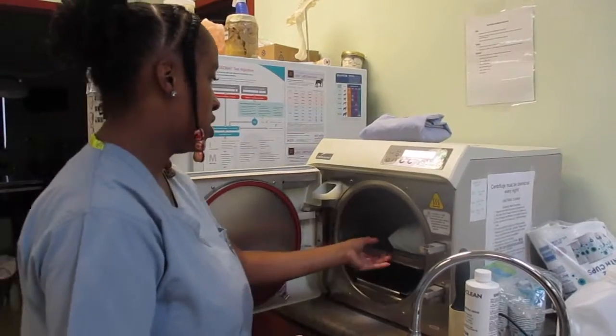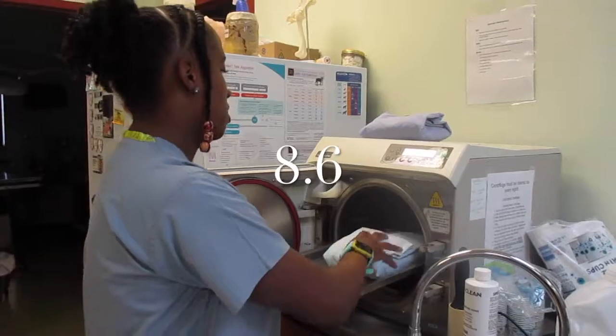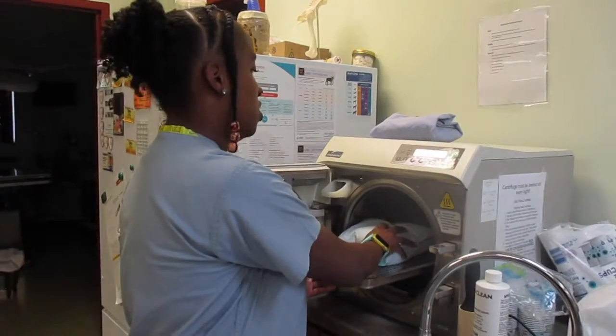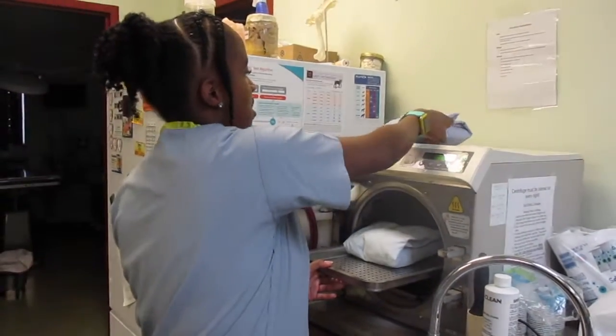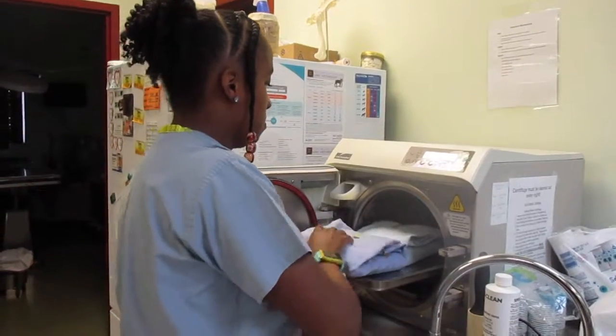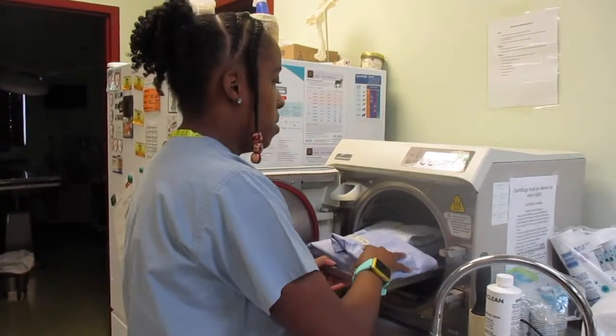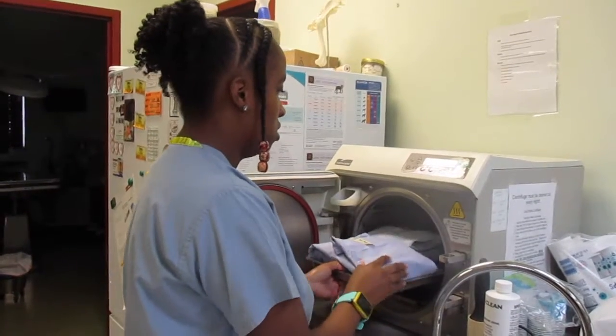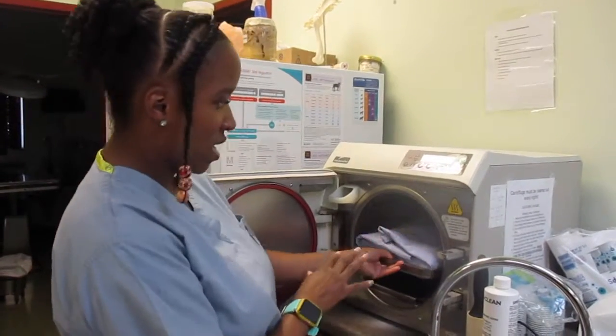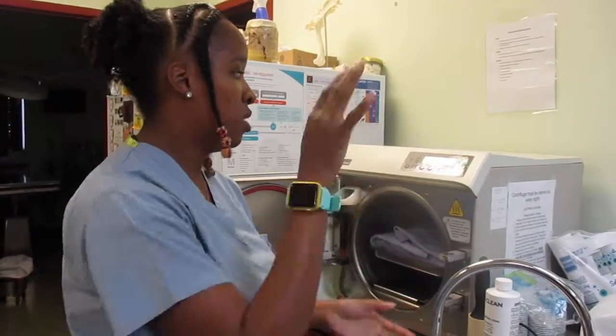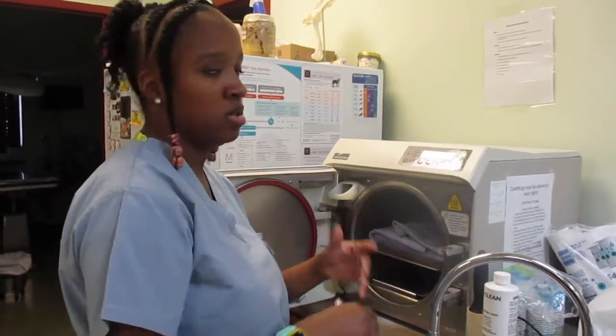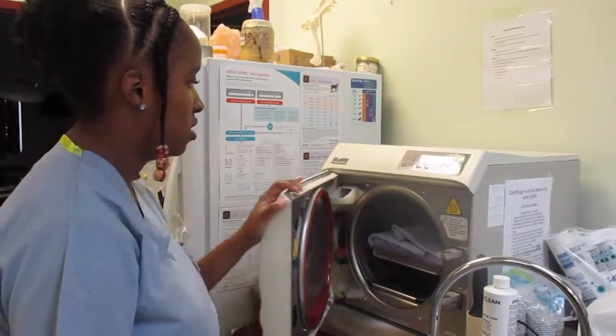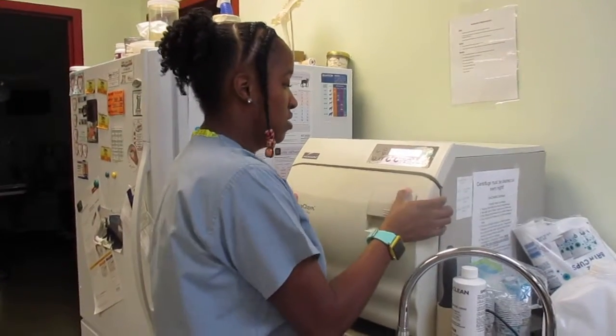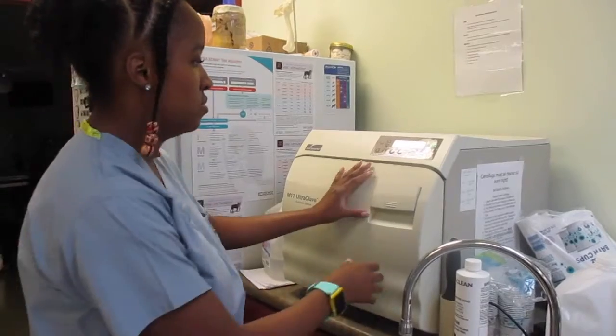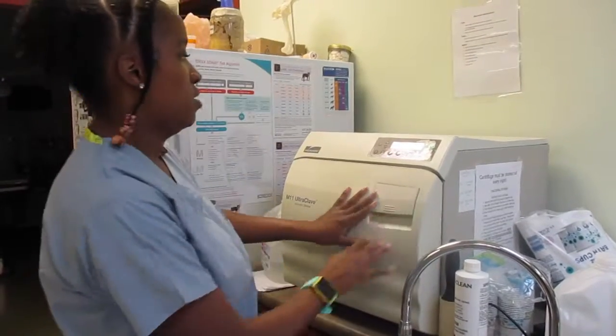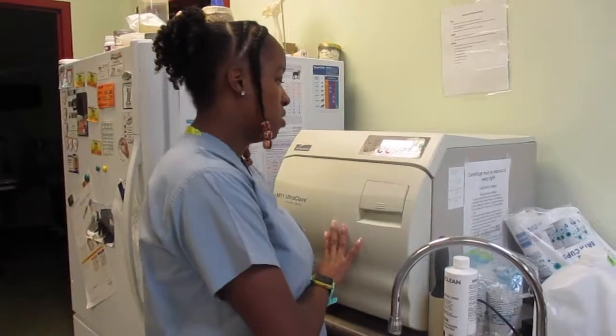So packing an autoclave, when you do pack an autoclave, you want to make sure that the packs are nice and flat and that they're not bumped up against the walls at all, and there's an actual small gap in there so the steam can actually get around the packs and sterilize them effectively. Also want to make sure the door is locked when you, there we go.